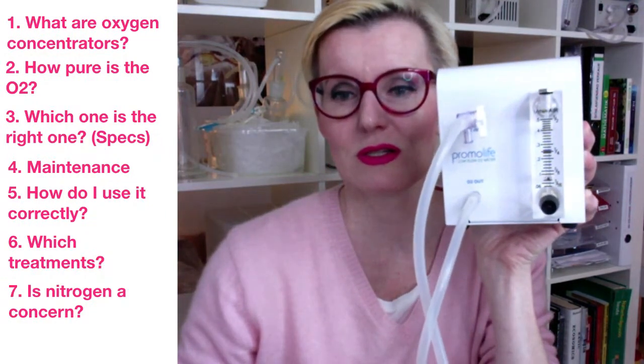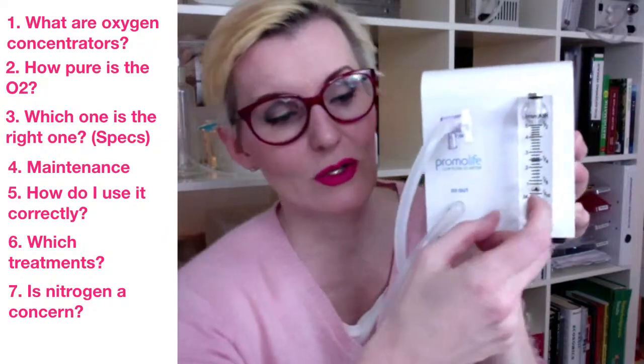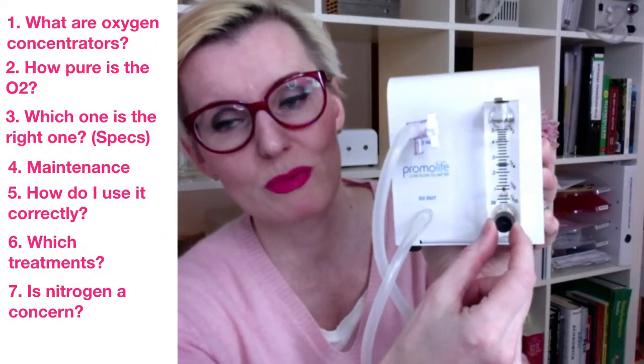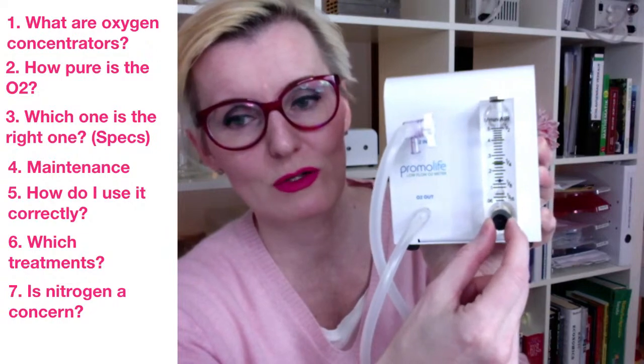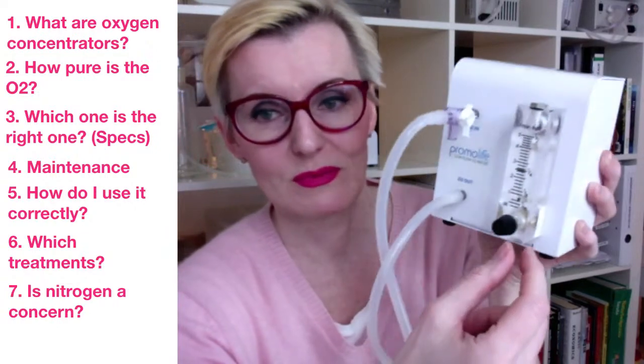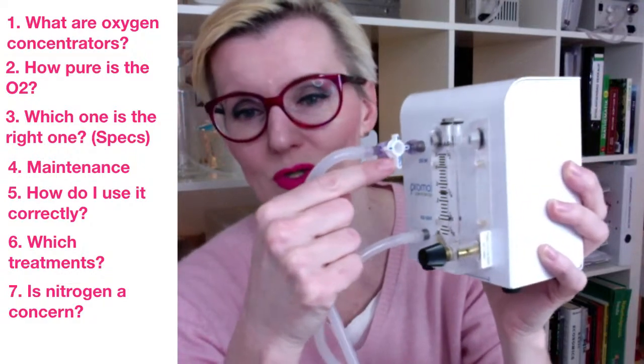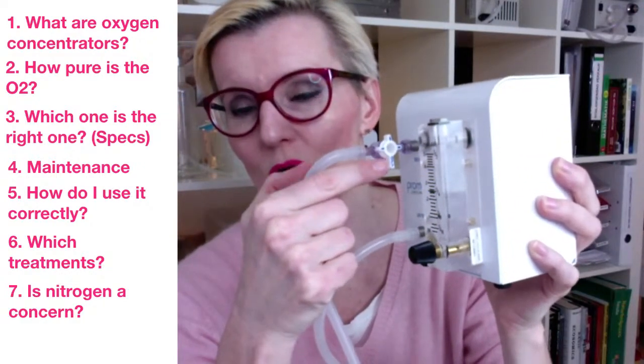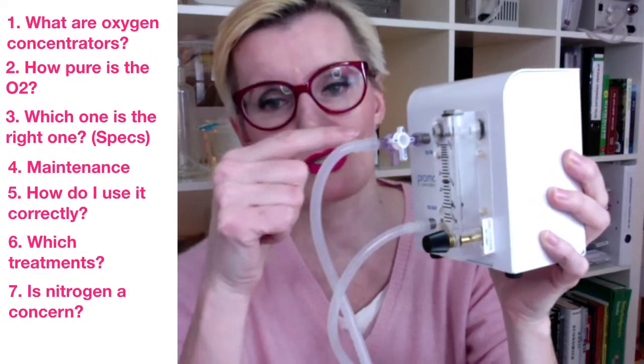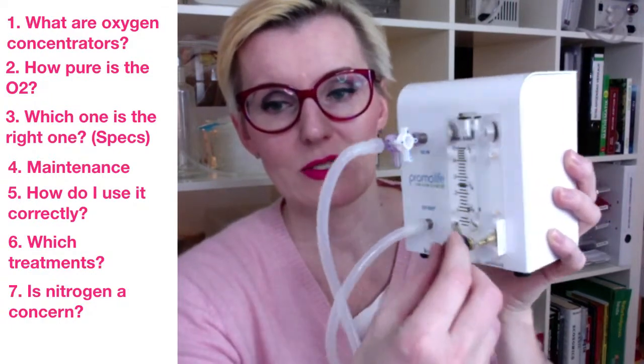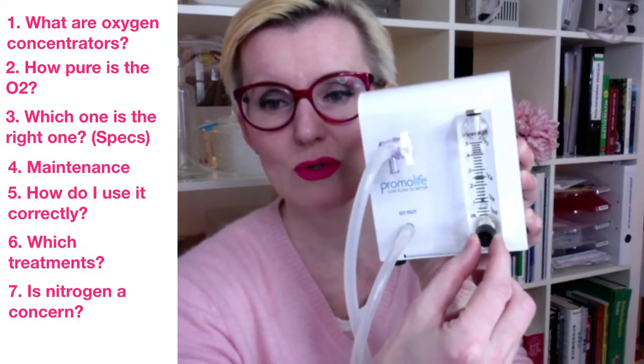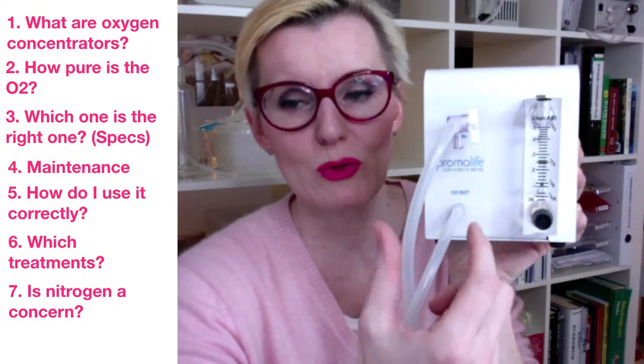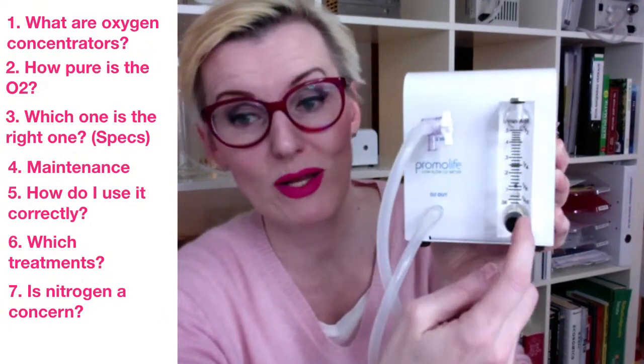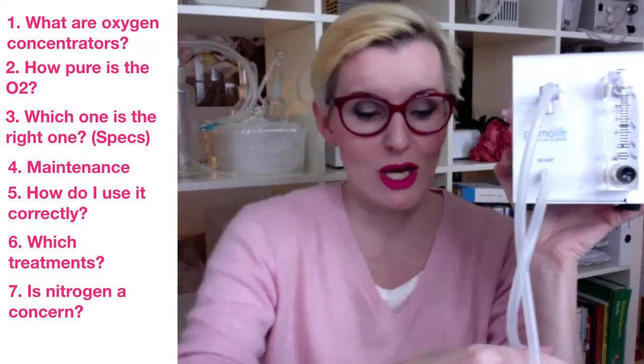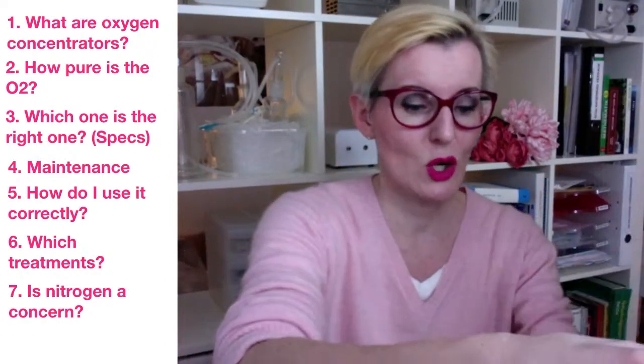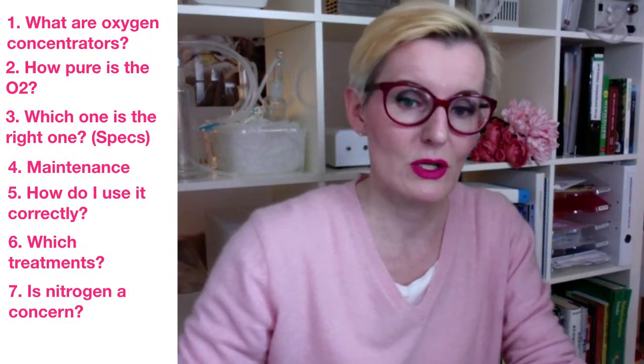And there's a lot of light here, so I'm not sure you're seeing this correctly. Okay, so here I can set this to those minimal flows that are required for ozone treatments. Here's another close-up, you see there's an off valve. So now the oxygen is flowing in here, and I can set the correct flow with this knob. If I was doing vaginal insufflations, for example, I would set it at 1/8 of a liter per minute, and then it comes out here through this tubing and goes into the ozone generator.